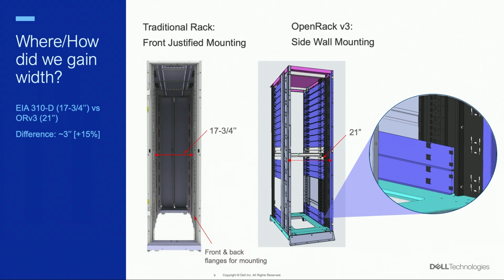And the other great thing is that we are doing this with exactly the same cabinet footprint. We are not changing anything. Traditional cabinets have front and back flange mounts for mounting the devices on the vertical rails, but we have taken out those flanges and a little bit of the rails, and we are using wall mount clips to hold the rails of each server, of each sled. We are able to gain pretty much 3 inches. So from 17.75, we are able to use 21 inches of width in a rack, which is more than 15%, which is great. Even without changing the footprint of the rack cabinet, we can still do the same space allocation in our data centers as we used to.